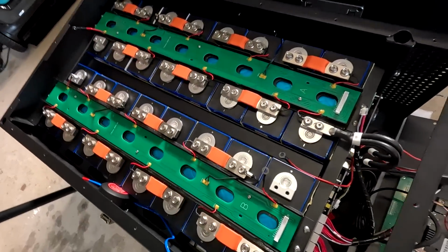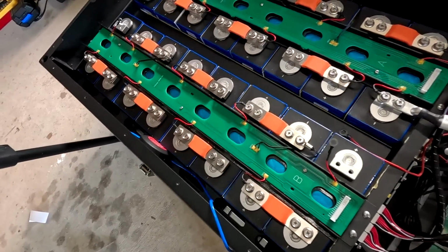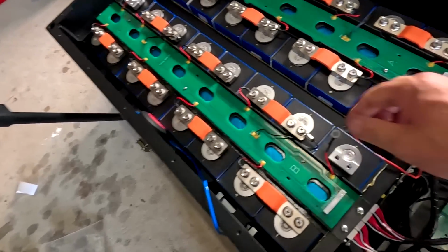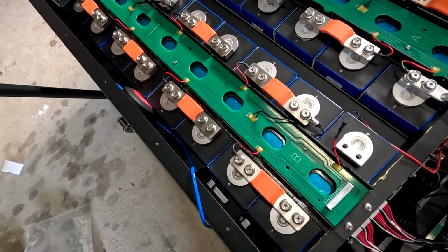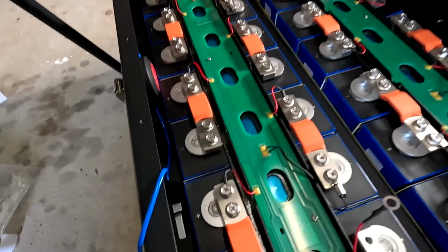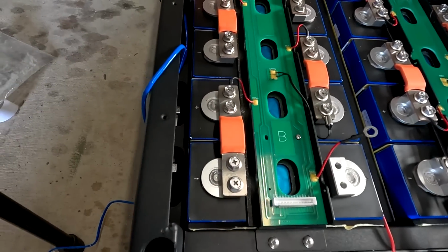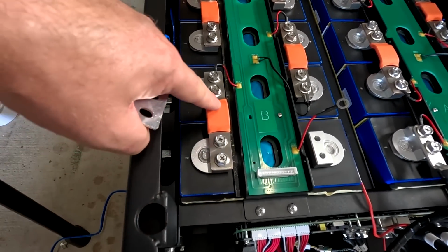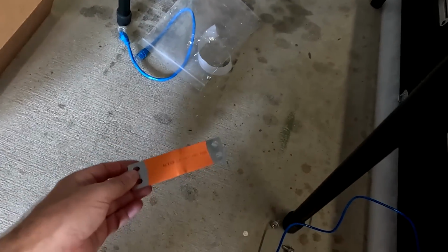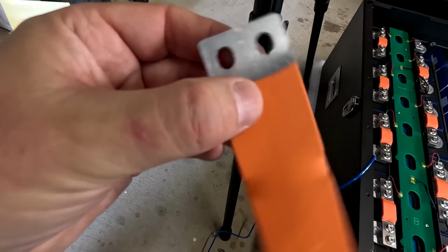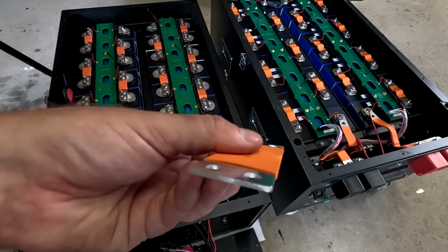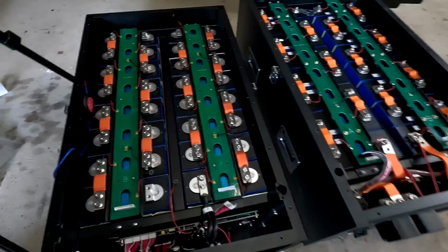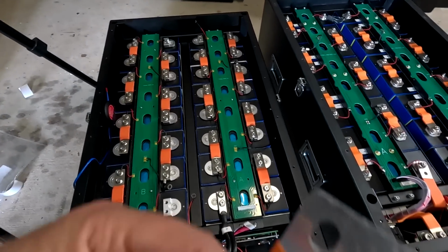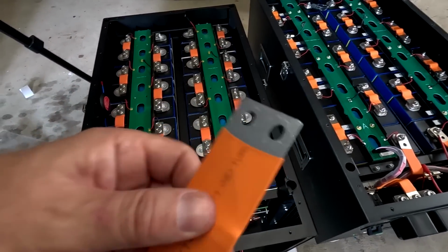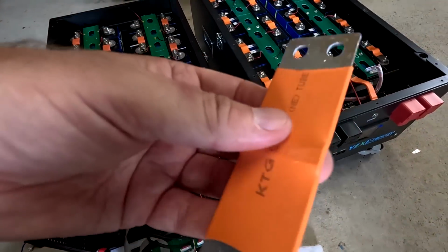So I've now connected all the bus bars, double bus bars to the battery terminals, including the balance wires and also temperature sensors where they belong. I haven't put in the last bridge over there because I wanted to show you. So these are all flexible copper bus bars here, multiple layers, makes it flexible in this hump. This one here is aluminium. Yeah? That's an aluminium bus bar. The resistance of this bus bar is maybe actually smaller than one of these bus bars, just because of the larger dimensions. But it is interesting they put a piece of aluminium in here.